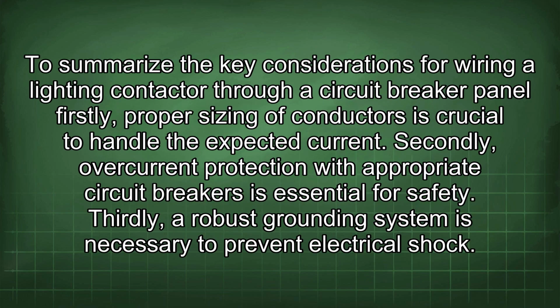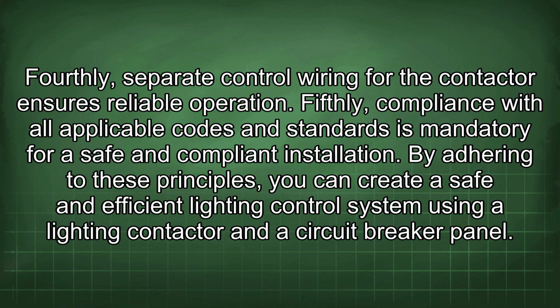To summarize the key considerations for wiring a lighting contactor through a circuit breaker panel, firstly, proper sizing of conductors is crucial to handle the expected current. Secondly, overcurrent protection with appropriate circuit breakers is essential for safety. Thirdly, a robust grounding system is necessary to prevent electrical shock. Fourthly, separate control wiring for the contactor ensures reliable operation. Fifthly, compliance with all applicable codes and standards is mandatory for a safe and compliant installation. By adhering to these principles, you can create a safe and efficient lighting control system using a lighting contactor and a circuit breaker panel.